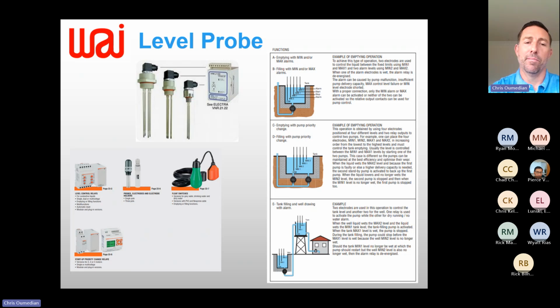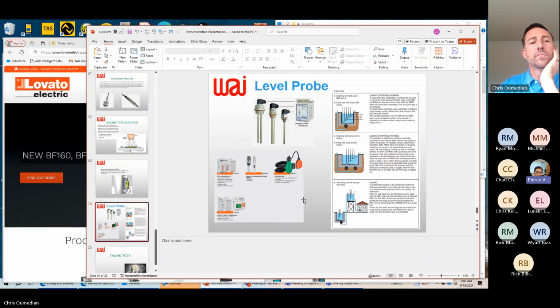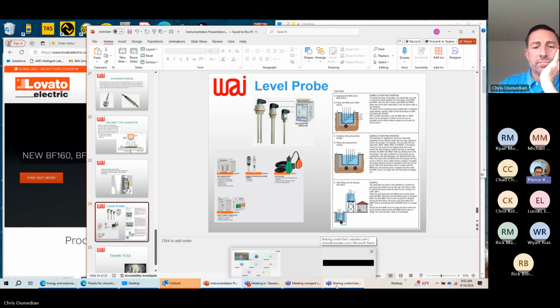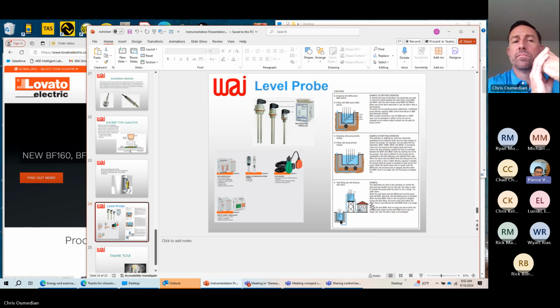It happens a lot. Oh my gosh, we're on another project out in Arizona where we've been extremely careful monitoring the installation and cable selection, and that project still had issues. So this subject next week is going to be really important, cable selection for pulsating power supplies, of which a variable frequency drive, a DC drive, a soft start are all big pulsating power supplies. If you want these sensors Chris presented on today to work, you're going to have to get your P's and Q's correct on your cable selections. It happens all the time.